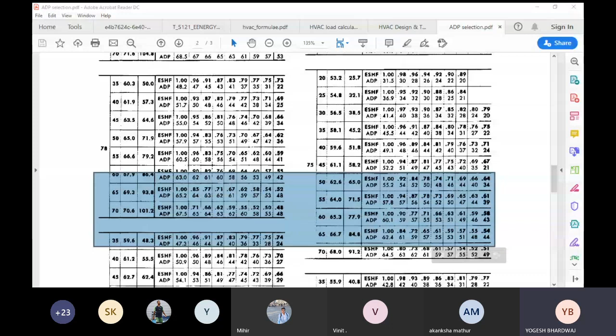This is the formula which is used to calculate the supply airflow. First, what does supply airflow mean? Supply airflow we also call dehumidified CFM. Supply airflow is the minimum amount of airflow that is required to achieve thermal comfort. So supply airflow is equal to total space sensible heat divided by 1.09 into 0.9 into (RT minus ADP). 0.9 is the contact factor, because we consider 10% of the air bypasses the cooling coil.